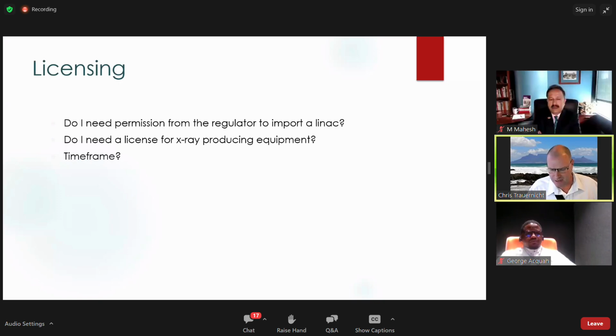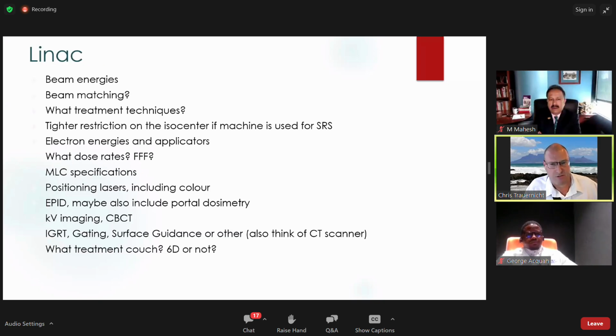And for the LINAC, I mean, the usual stuff would be beam energies. What photon energies do I want? If I have an existing LINAC, do I want beam matching? What treatment techniques do I want to treat? So for example, if you're going to treat radiosurgery, you need tighter restrictions on the isocenter. If you don't ask for it, you may not get it and you can't demand it afterwards. So this is a good time to sit down with your oncologists and think, what treatment techniques do we want to treat, and specify accordingly.